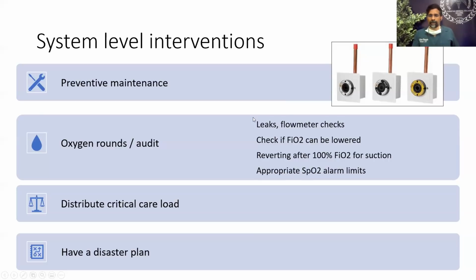Now, we have therapists who go around looking at the ventilators and their settings every hour. So they also can look for leaks, to see if there's any leak at the cuff or in the tubing. Flow meters: sometimes flow meters are left open on the wall, or sometimes when a flow meter is being used, it is turned up so high. We want to use 15 liters per minute, but sometimes it's turned up so high that the flow is actually much higher than 15. But because the flow meter can only show a maximum of 15, the indicator stays at 15, and there might be much higher flows going through. So it's important to look at these things.